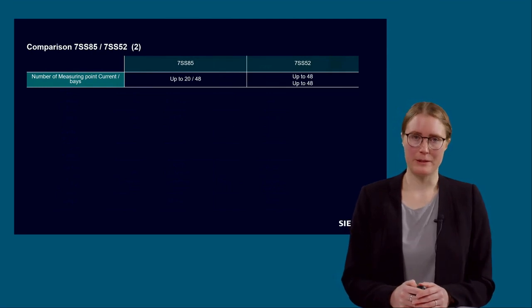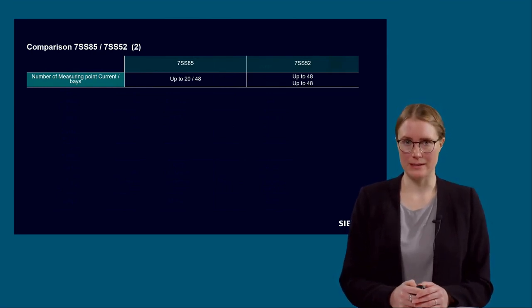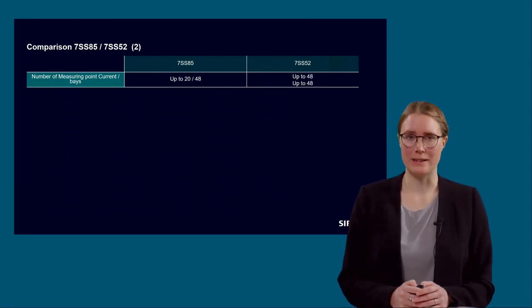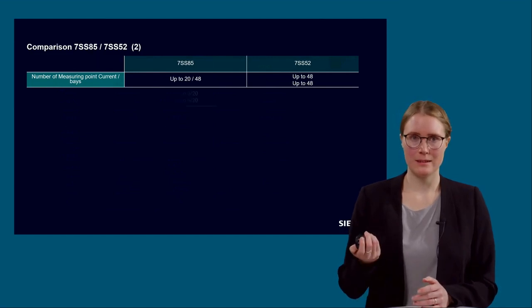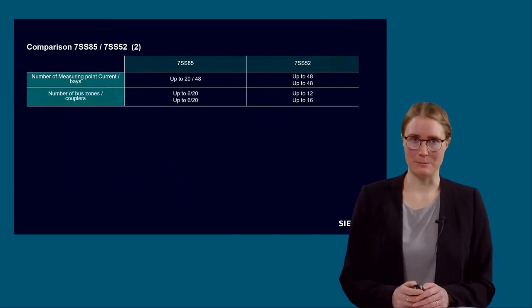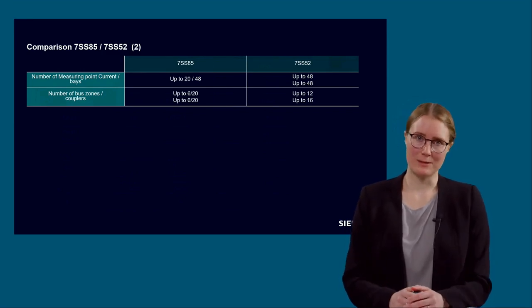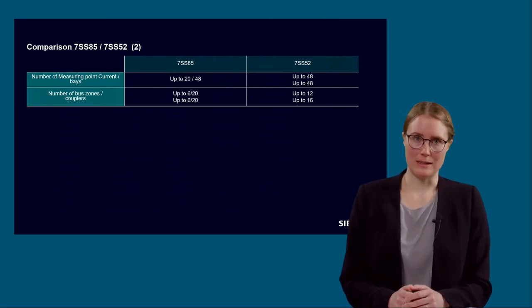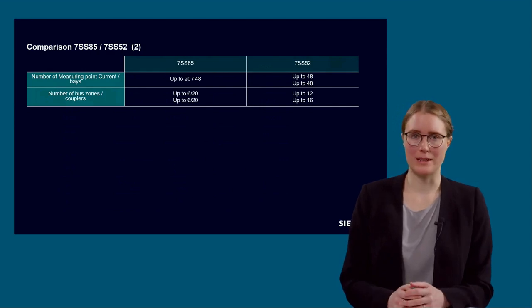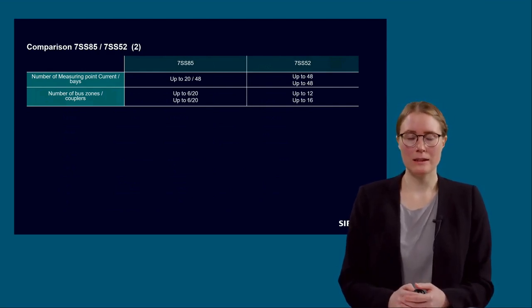The maximum number of measuring points is 20 for the 7SS85 centralized and hybrid solution, 24 for the distributed IEC 61850 compliant solution, and 48 for the 7SS85 CU solution. For the 7SS52, the maximum number is also 48. The maximum number of bus zones are 6 for the 7SS85 centralized and the IEC 61850 compliant solution, and 20 for the 7SS85 CU solution. Same with the maximum number of couplers. For the 7SS52, up to 12 bus zones and up to 16 couplers are possible.